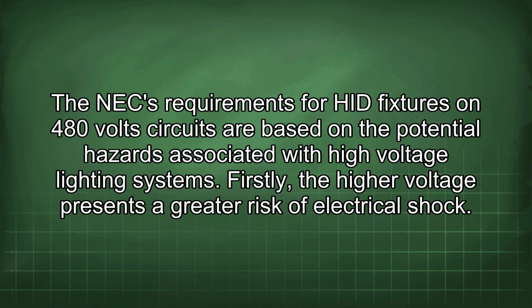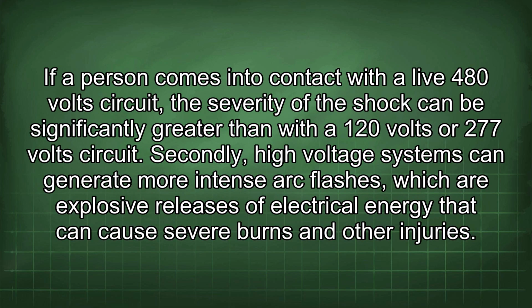The NEC requirements for HID fixtures on 480-volt circuits are based on the potential hazards associated with high-voltage lighting systems. Firstly, the higher voltage presents a greater risk of electrical shock. If a person comes into contact with a live 480-volt circuit, the severity of the shock can be significantly greater than with a 120-volt or 277-volt circuit.